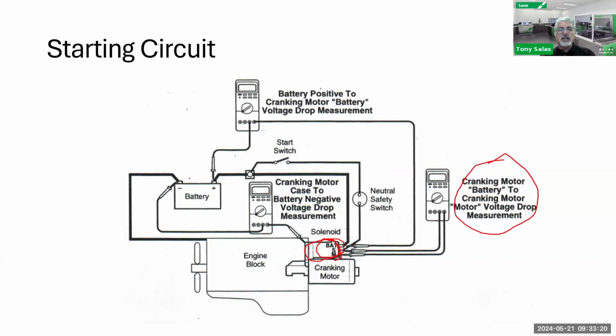Starting with negative, we see the negative post, and our meter testing the case. This is where we see the most problems on light duty and medium duty trucks: the grounding to the chassis. You'd think it's easy, but no, because you've got the negative battery going to the chassis somewhere, and then from the chassis another cable that could go to the block or directly to the starter motor, depending on the setup. So you might have multiple connections on the ground side, and that's where we see a lot of issues on the negative battery post — a high voltage drop there.